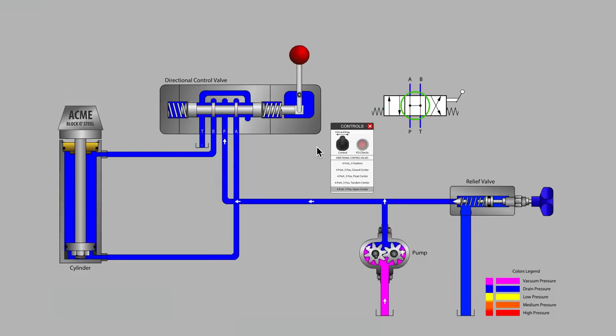both the open and tandem center valve unload the pump when returned to center. In so doing, a simple fixed displacement pump can be used without passing flow over the relief valve when the system is in neutral. Heating and energy draw is thus minimized.